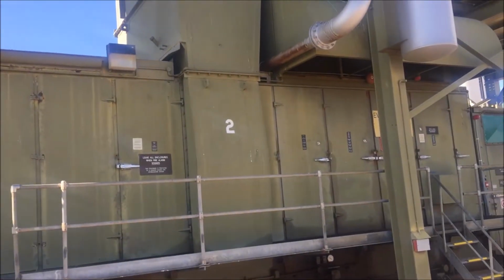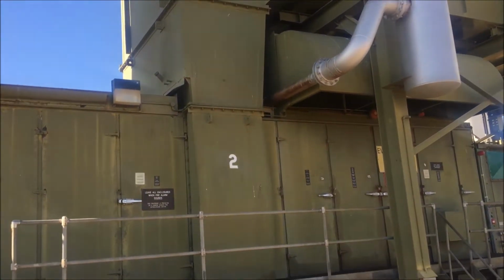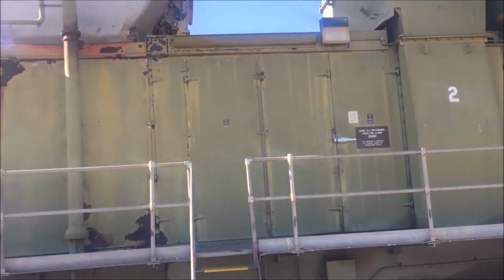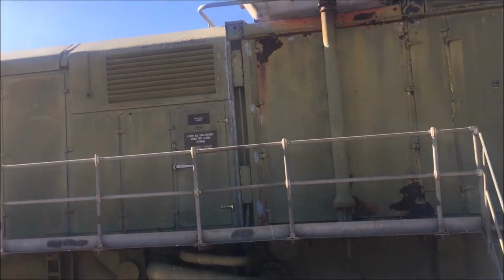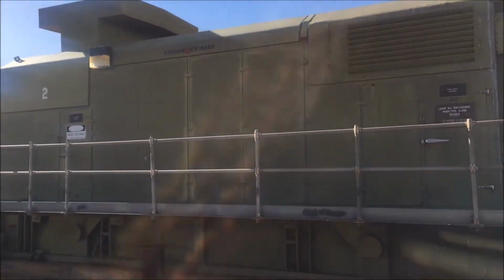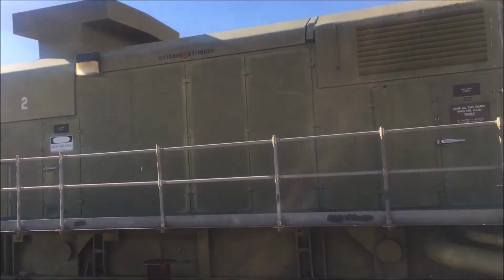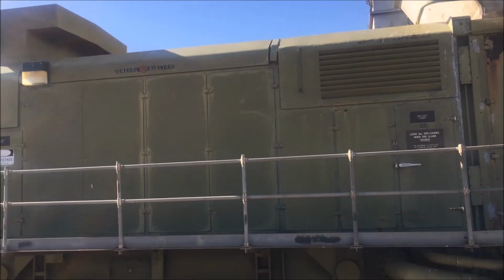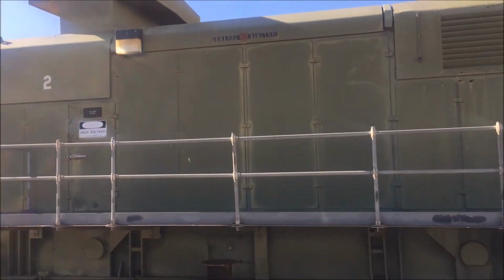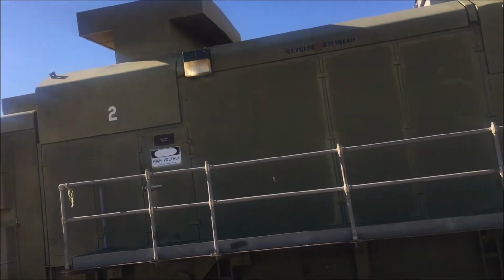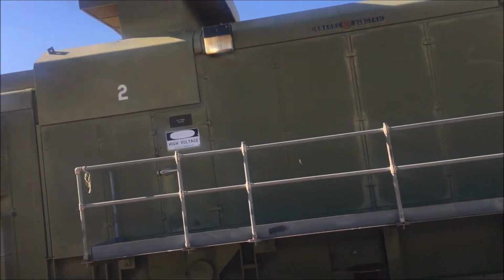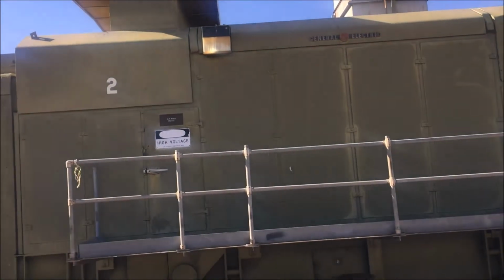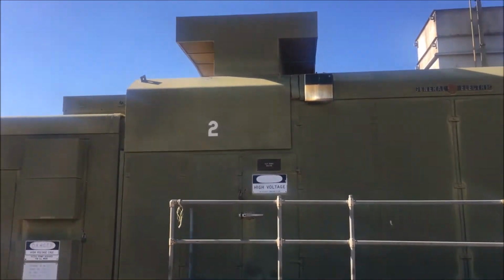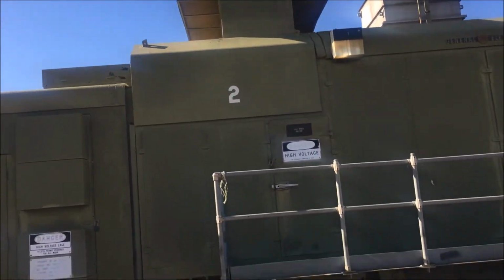Trouble is, 40 megawatts of that is used for the compressor section. That leaves you 30. Then it uses 5 for the excitation of the generator and all your auxiliaries, which leaves you 25 megawatts left over. That's the generator section there. I can't get inside and look at it because it's not ours anymore. This is about as close as I can get. Just the cooling for the generator.